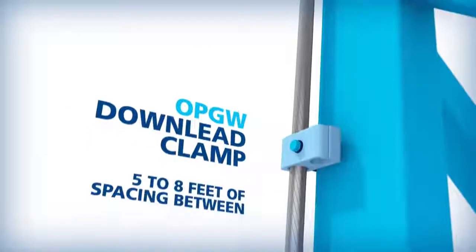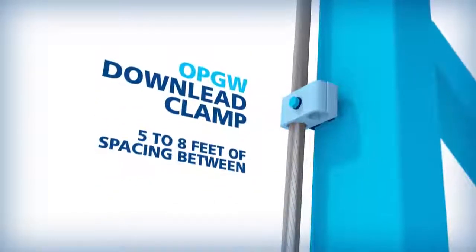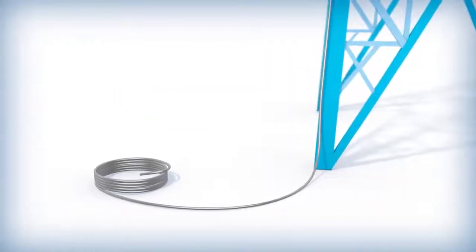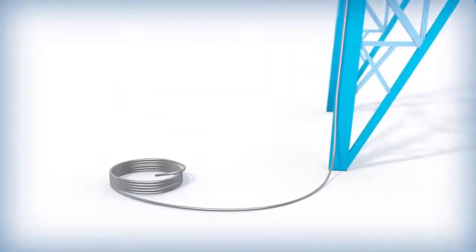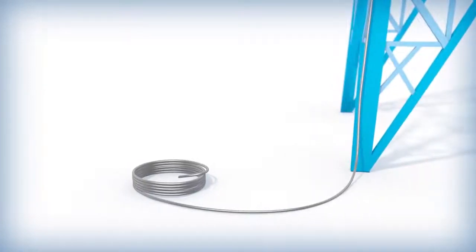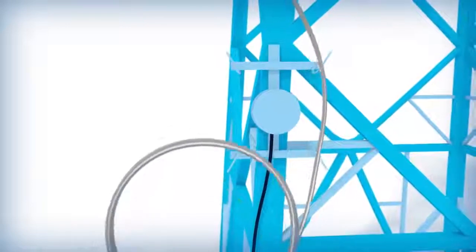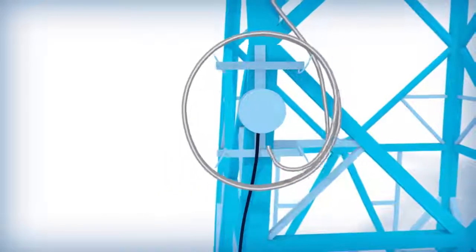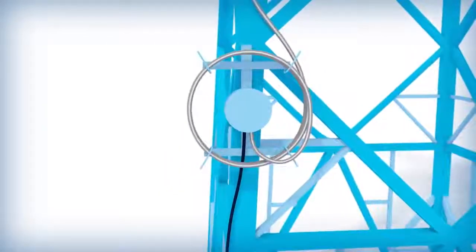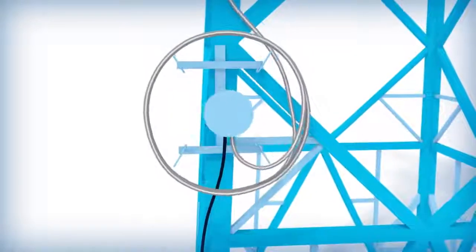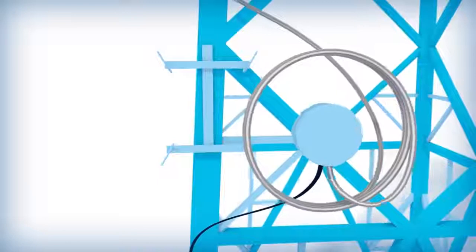The OPGW is trained down the structure using down-lead clamps. In order to provide enough cable for splicing, the OPGW should extend beyond the bottom of the structure and be looped in coils for storage. To prevent damage, the coil should be fixed on the structure at the splice enclosure location. For future splicing and or maintenance, the splice enclosure may be removed from the structure and brought to ground.